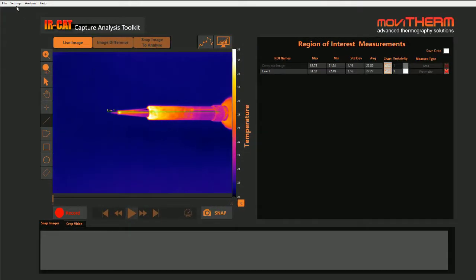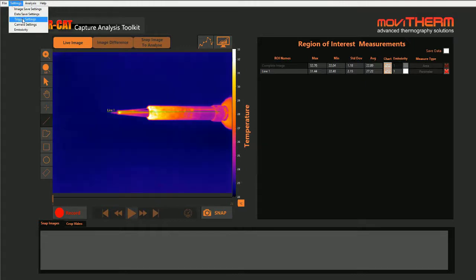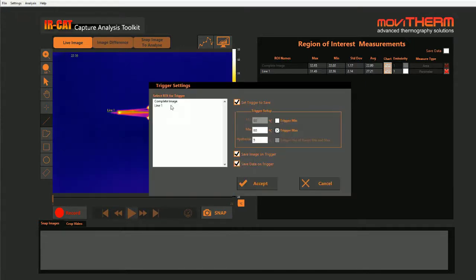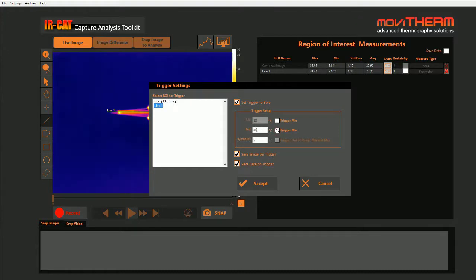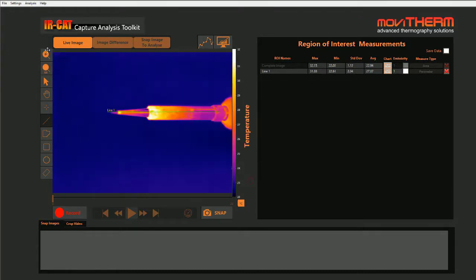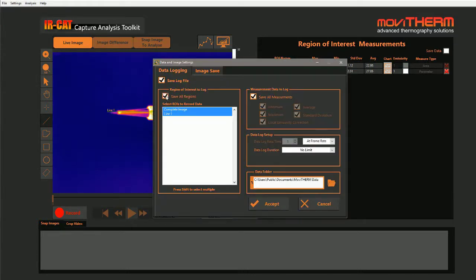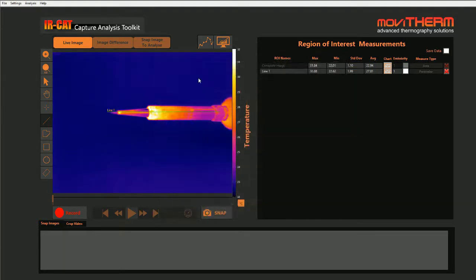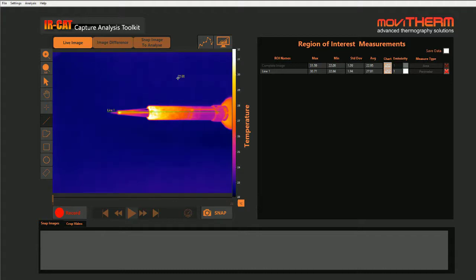The ROI trigger feature allows you to trigger temperature alarms or events without requiring any external I/O hardware. Just set the trigger criteria and the threshold based on measured temperatures in the region. When the trigger conditions are satisfied in the region of interest, the trigger action is executed. This feature can be used to capture images or data only when a predefined condition has been met, such as when the maximum temperature in a region exceeds a preset alarm limit.